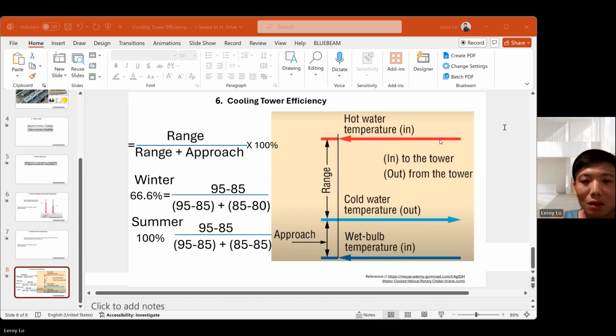You can see the only factor that is changing for this calculation is the wet bulb temperature. Once that increases, for example in an extreme case, you might have zero at the approach, which will make the efficiency 100% in your calculations. As you can see, it's range over range, so that's 100% automatically, which means you cannot remove more heat. So if you're running into this kind of question, you have to have another cooling equipment such as another evaporative cooling system, or have more coolants.